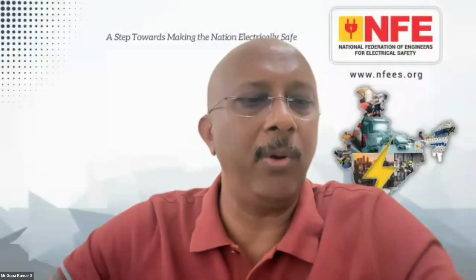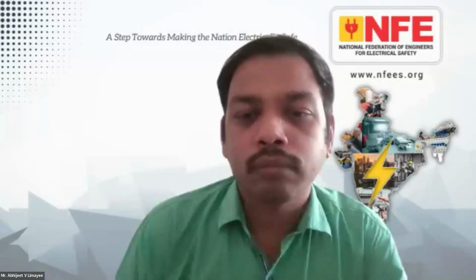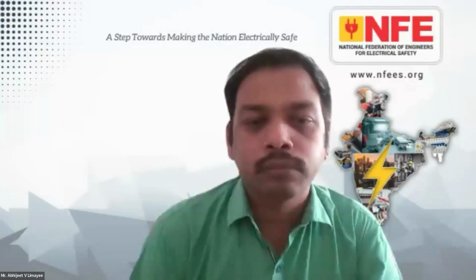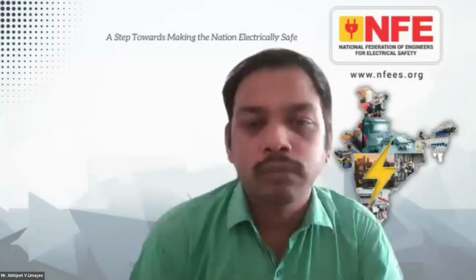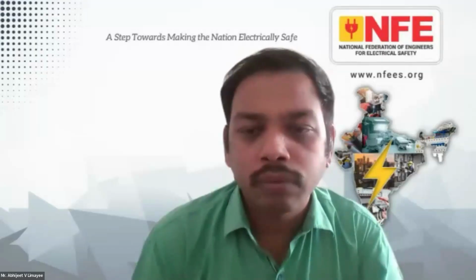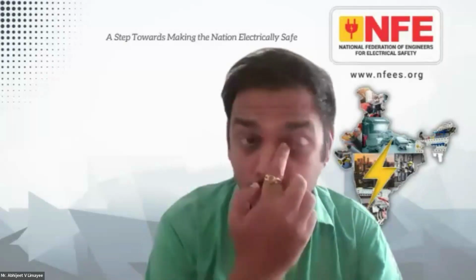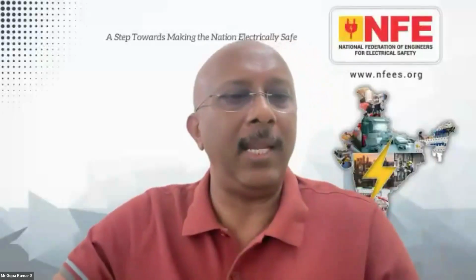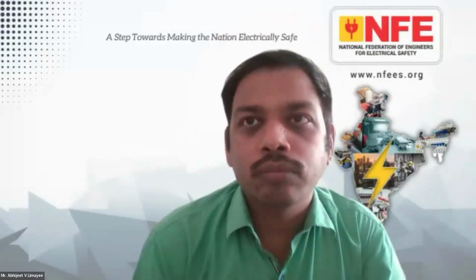Yes. Probably I will make a question. Mr. Abhijit, you know very well that IoT is a very good tool for supervision, data collection, communication, and all. But protection is localized. The protection should be localized. That means if you have a circuit, the circuit has to be protected. That is the concept, not what is claimed. Also, the principle of discrimination between two protective devices, between two circuits, is important. The device is violating it, which can create a problem to the user. Now, my question to you is, should such a device at the main panel be used in a hospital? How does it discriminate between various group locations? And what is the danger of using this kind of device in a hospital, and what kind of problems may occur?